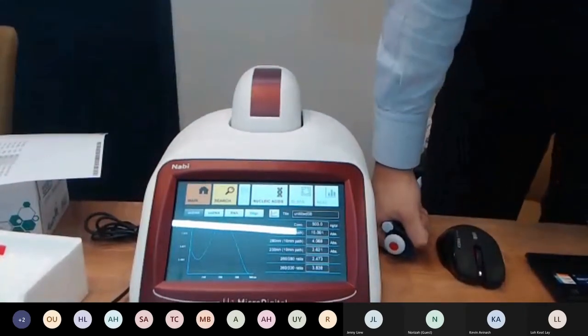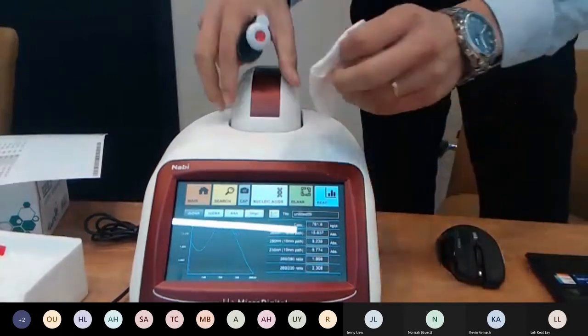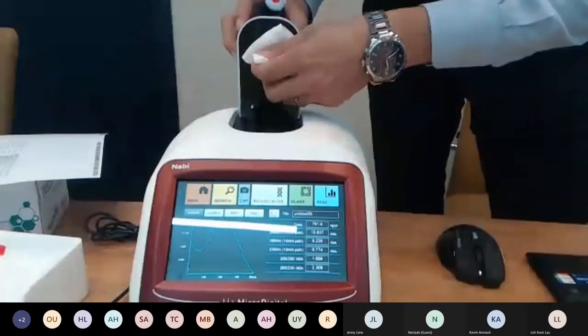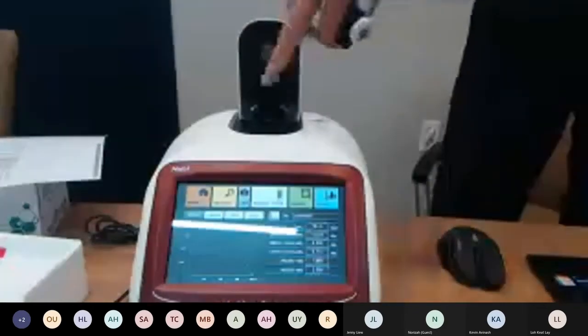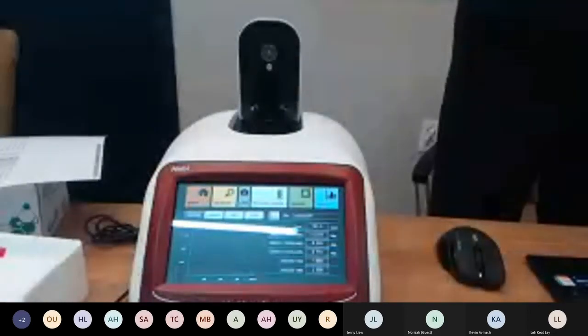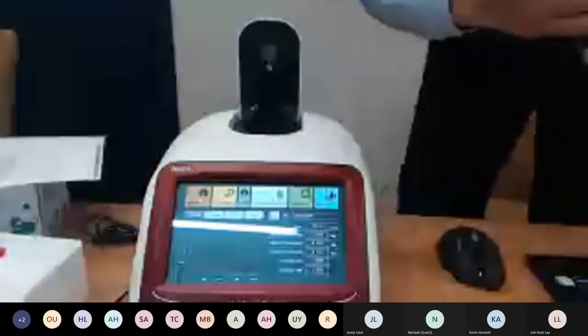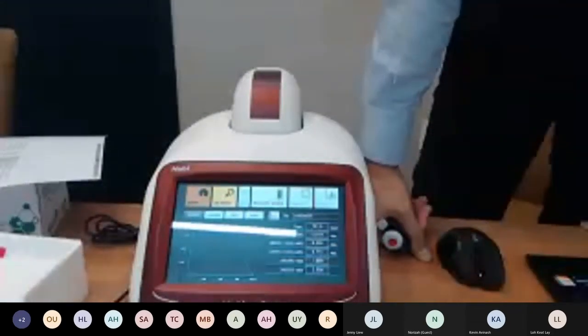When you're done measuring, make sure to wipe the pedestal clean. I'll also show you the 1,300 ng/µL sample — which should be around 1,350. Because this is a medium concentration, you'll be able to hear two measurement sounds — or possibly three depending on the concentration.